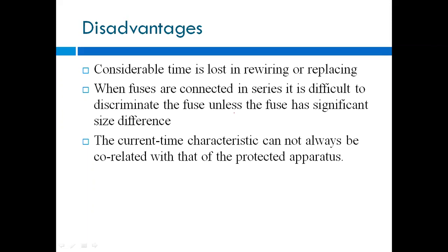The second disadvantage is that when fuses are connected in series, it is difficult to discriminate between the fuses unless the fuses have a significant size difference. When we connect these fuses in series, it is difficult to differentiate if there are a number of fuses in series. We cannot detect which fuse actually blew out. So that is a disadvantage.